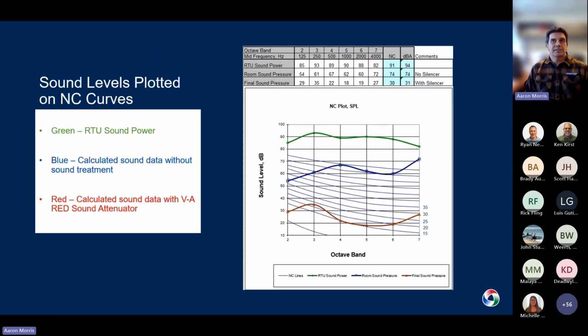Another way to visualize that, I've plotted it onto NC curves here using a tool from Kruger's website. It's a free download, a little noise calculator. It gives you spots to plug in up to 4 different runs. You plug in each octave band from the 125 hertz up to the 4,000 hertz. And then it plots it onto the NC curve and calculates the NC level and the dBA level.